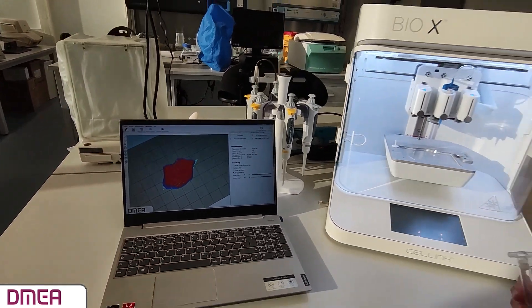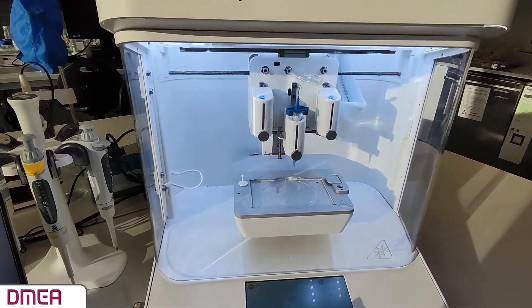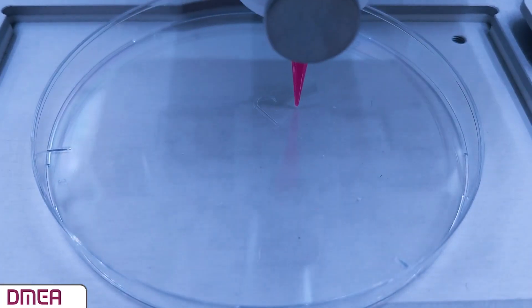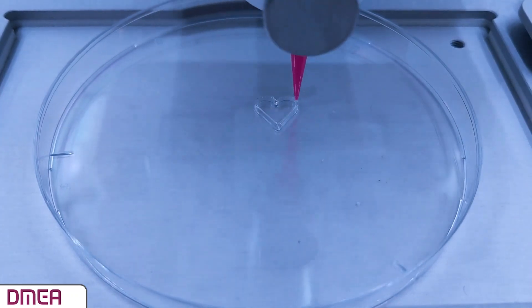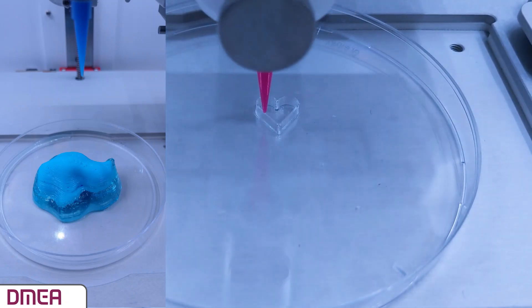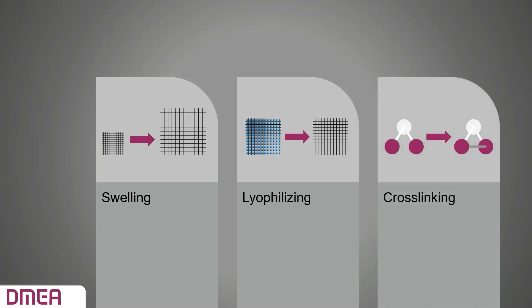The hydrogel developed for this project is called GAL Bio-Ink, and it contains gelatin, alginate, and laponite. The cartridge with the hydrogel inside is connected to air pressure, and by starting the print, a 3D structure is built layer by layer. In order to print an LAA occluder with good print quality, a support structure is necessary. After the print is completed, the material is swelled to create a porous structure, then lyophilized and cross-linked so there are stable chemical bonds.